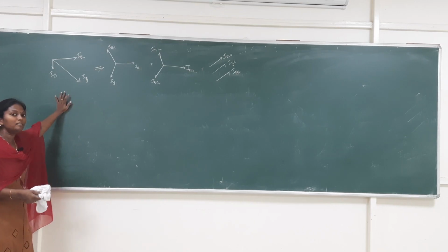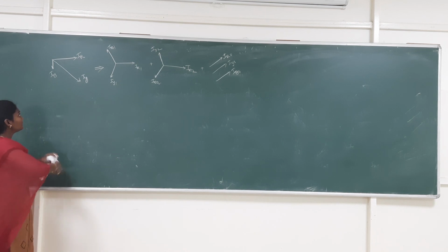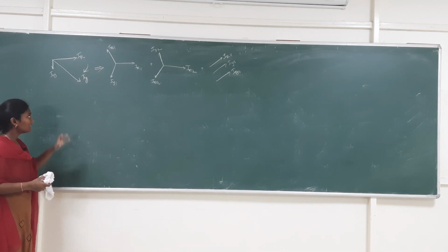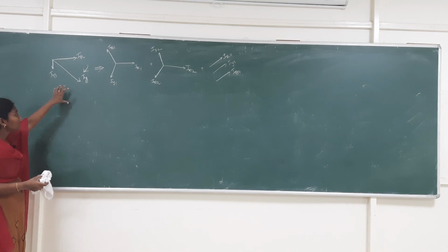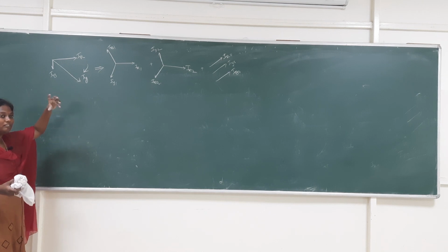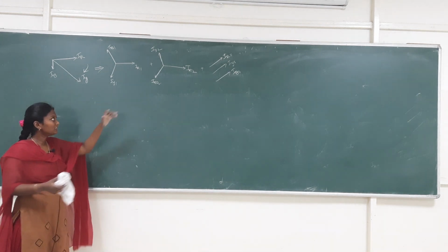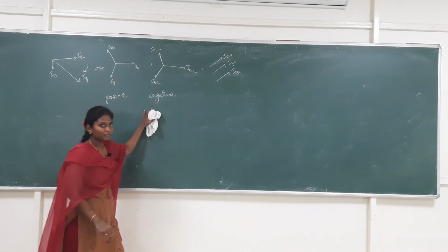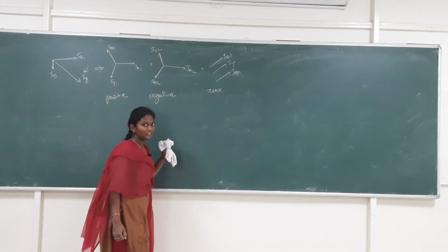This is my unbalanced original system. It follows the RYB sequence. It is unbalanced because the magnitude of current flowing through each phase is different, and the phase shift does not maintain 120 degrees. The system is under unbalanced condition, so it has to be resolved into three symmetrical components: the positive sequence, negative sequence, and zero sequence symmetrical components.